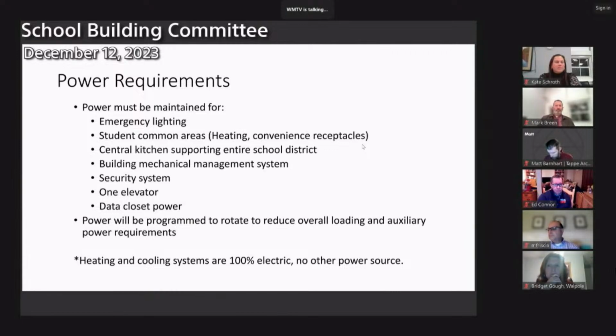Power requirements must be maintained for emergency lighting, student common areas, the central kitchen supporting the entire school district, the building mechanical management system, the security system, one elevator remaining online, and data closet power. Power will be programmed to rotate to reduce overall loading and auxiliary power requirements. As a reminder, heating and cooling systems in this building are 100% electric, with no other power source.